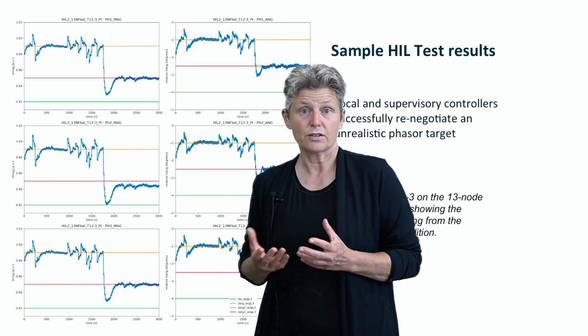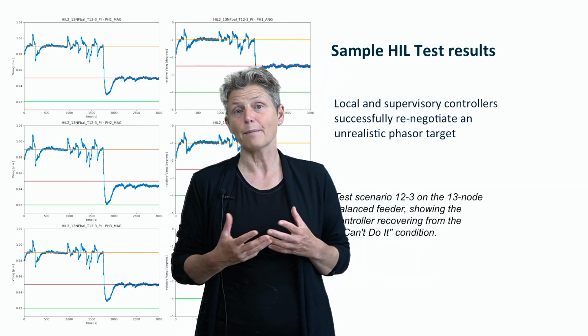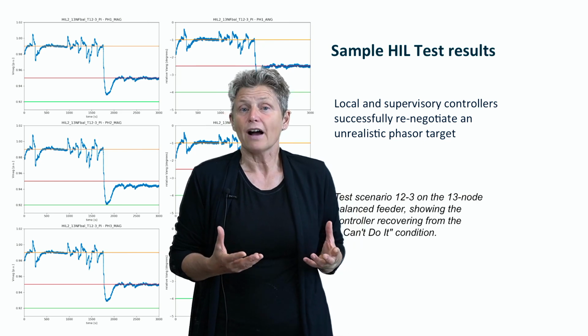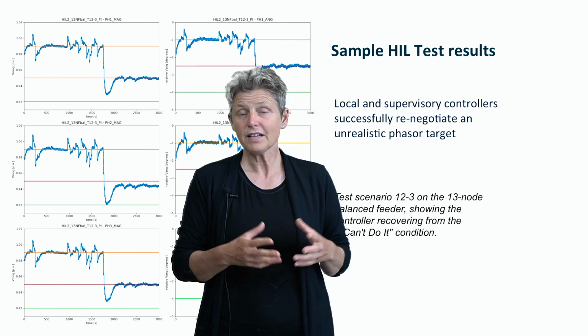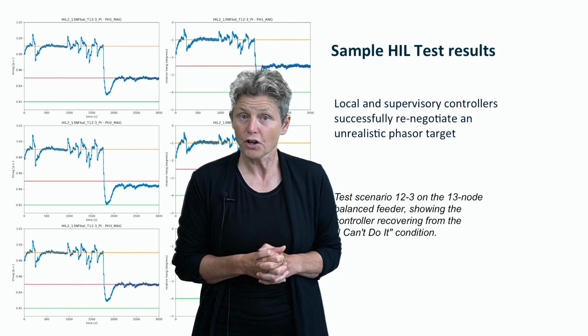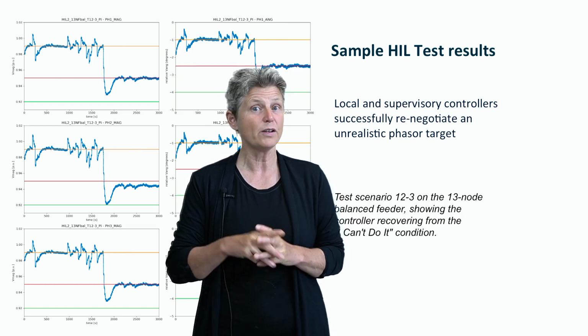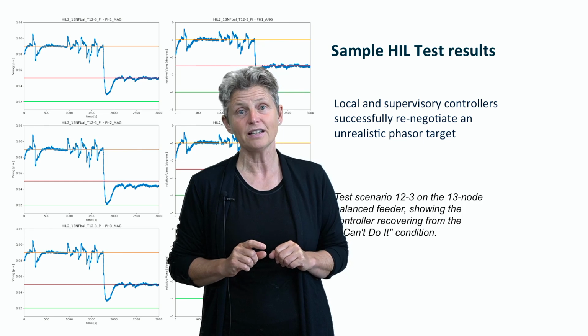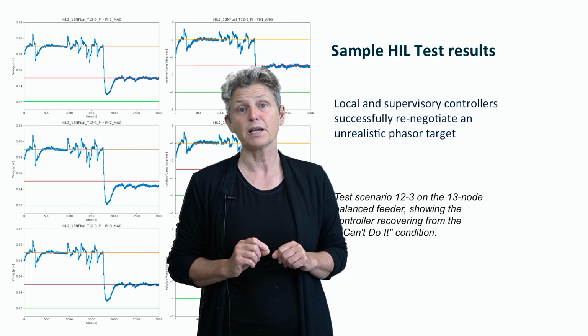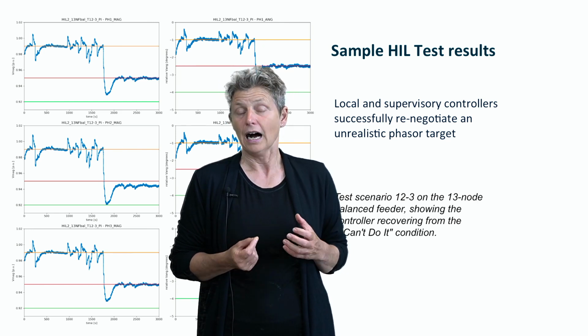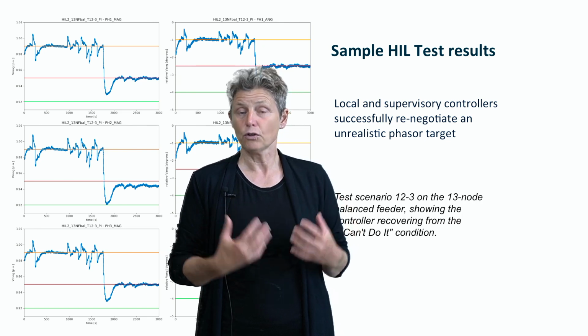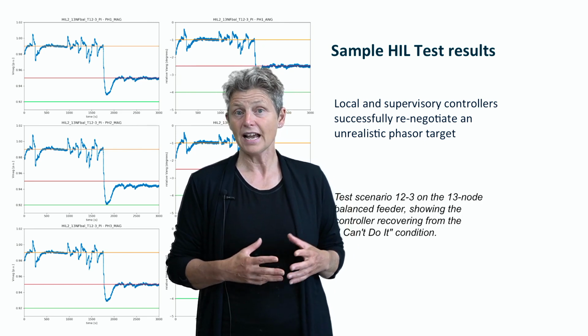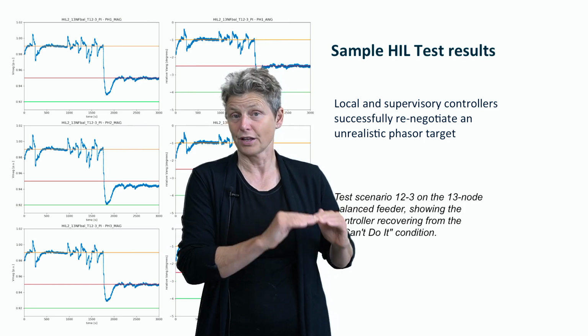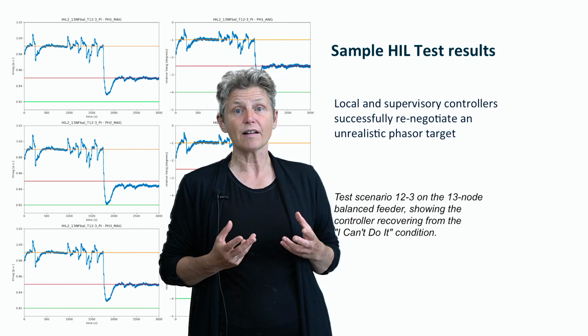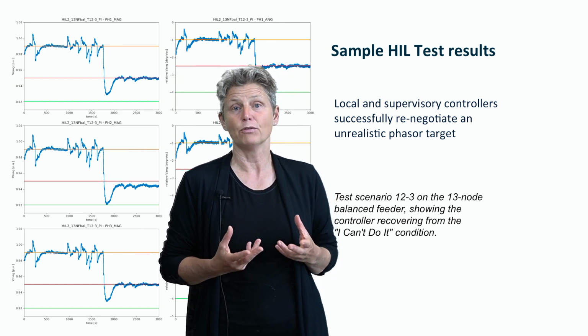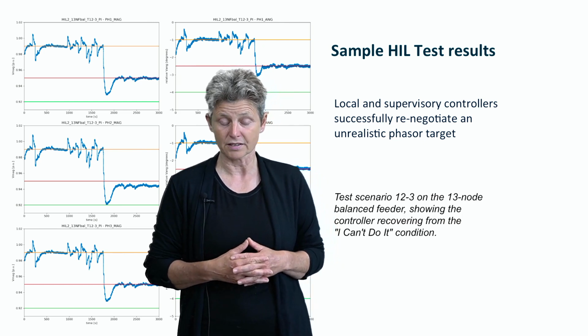Certainly, a vulnerability is a loss of communications, and so we've tested what happens when stuff drops out. Basically, we have to fail safe to revert back to a strictly local control. But what's noteworthy about the phasor-based control is that really there's only one remote stream of data that you need, and that's from the reference PMU. The reference phasor is the only non-local bit of information that you need in order to maintain the system and maintain the last published phasor target. So that's a comparatively low amount of information that has to be transferred on an ongoing basis.